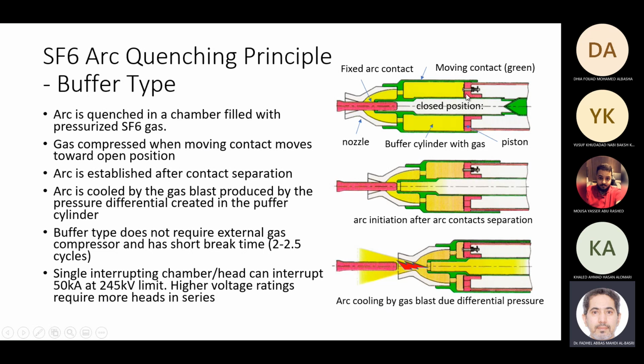The quenching principle is the same as I mentioned before. This I already explained. This is now in a closed position. The current flows. These are the fixed contacts, and the green ones are the moving contacts. The current flows from here through this and goes to the other side of the breaker. The yellow here is the SF6 gas. It is trapped in this chamber, in the cylinder here. When you try to open it, the pressure will increase, squeezed by this piston. Now there is no place for it to leak because of this closure here.